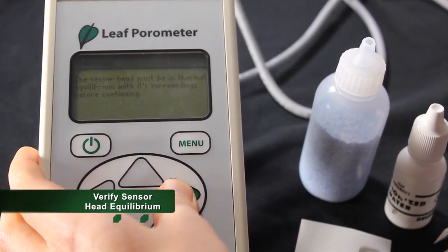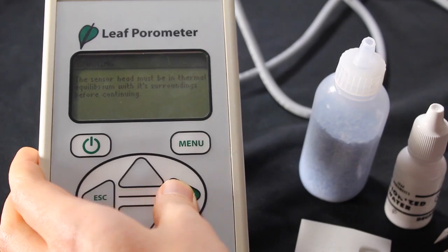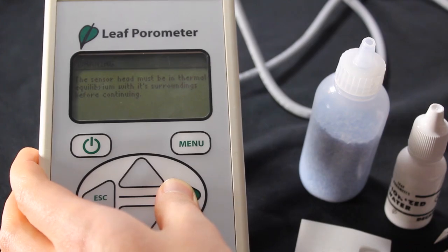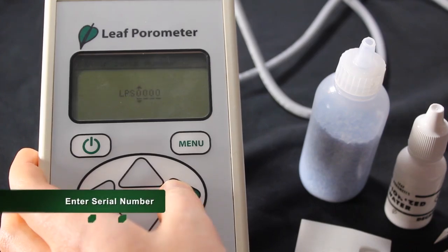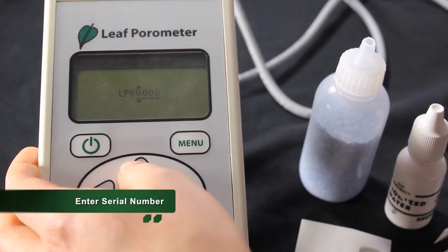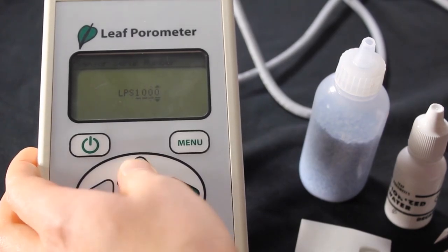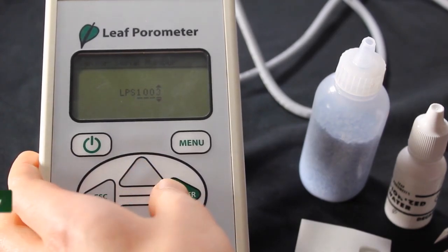It is important that the porometer sensor head, calibration block, and DI water are all in thermal equilibrium with the environment where measurements will be taken. It may take upwards of 10 minutes for this to happen, depending on the differences between storage and measurement conditions. The temperature of the sensor will display on the screen. Press Enter to proceed to the next step. You will be prompted to enter the sensor head serial number. This number can be found on a tag attached to the sensor head.